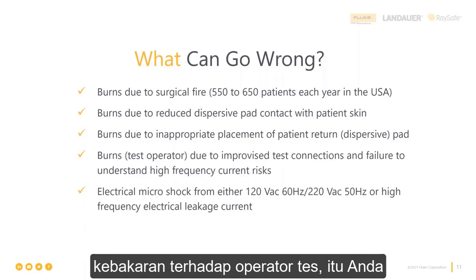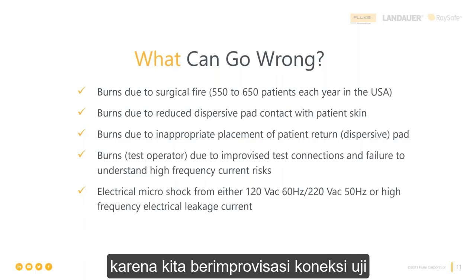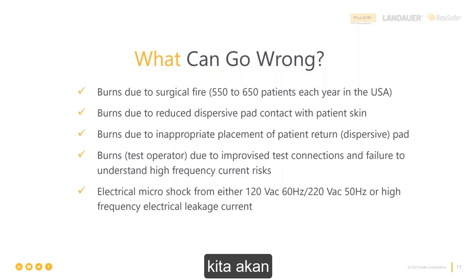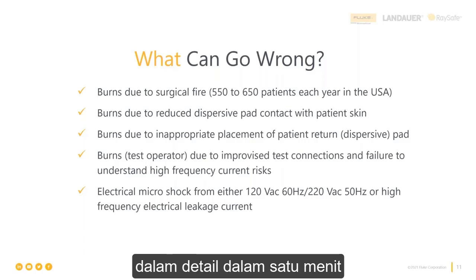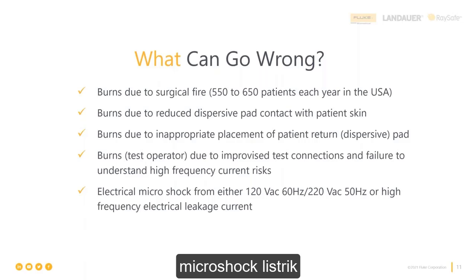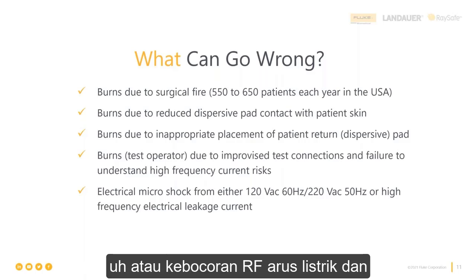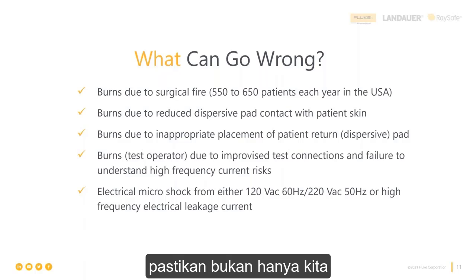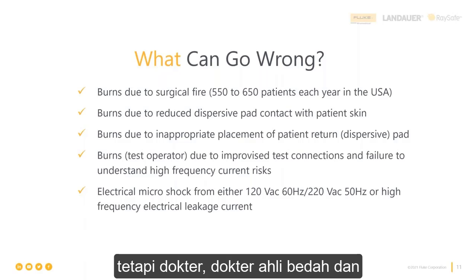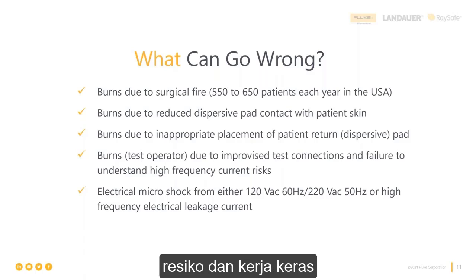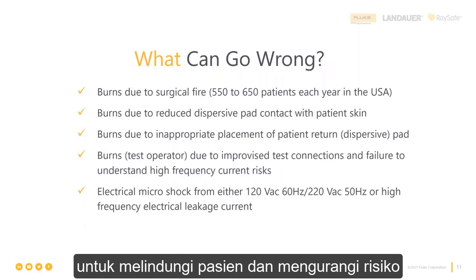Burns to the test operator, that's you and me, because we improvise test connections and fail to understand the high frequency current risks. We're going to talk about that in a little bit more detail in a minute. The electrical microshock from either regular mains power frequency or high frequency or RF electrical leakage current, we're going to talk about that a little bit later in the deck too. We want to be careful about these things, make sure that not only we, but the clinicians, the surgeon and the circulating nurse are aware of these potential problems and risks and work hard even during the actual surgical procedure to protect the patient and reduce risk of injury.